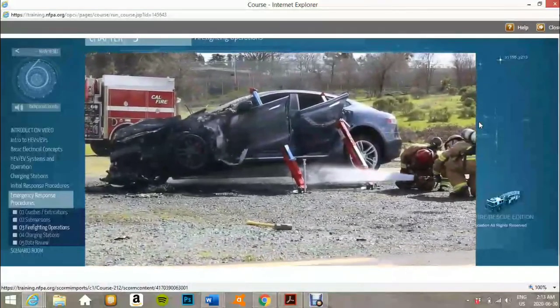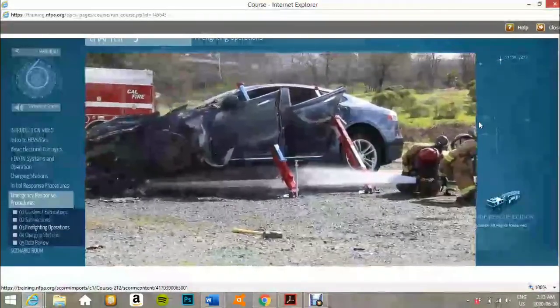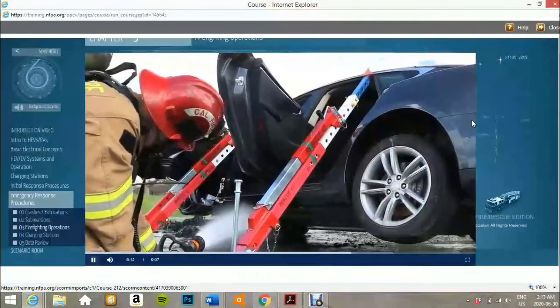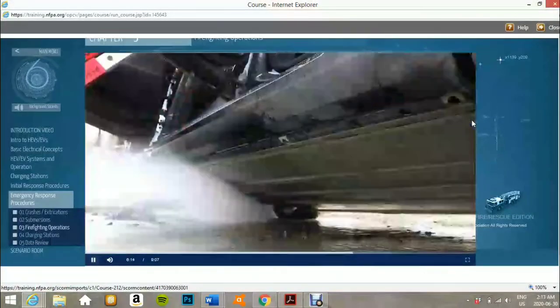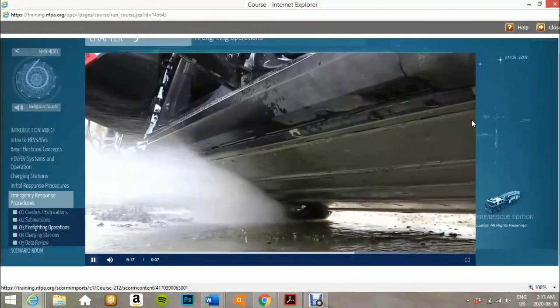Also, once the main body of fire is knocked down, especially if access to water is limited, consider a low-flow, low-pressure application to the battery case to reduce the amount of water that is deflected without contributing to the cooling process. If the decision is made to allow the battery to burn, be sure to protect any exposures.